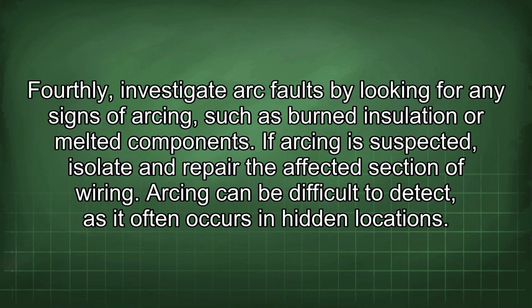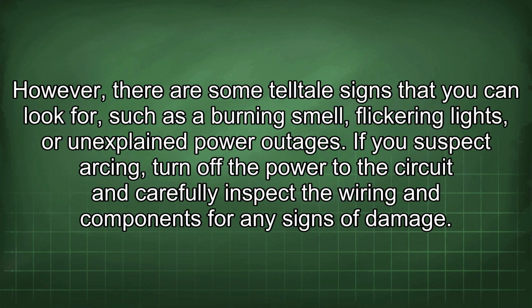Fourthly, investigate arc faults by looking for any signs of arcing, such as burned insulation or melted components. If arcing is suspected, isolate and repair the affected section of wiring. Arcing can be difficult to detect, as it often occurs in hidden locations. However, there are some telltale signs that you can look for, such as a burning smell, flickering lights, or unexplained power outages. If you suspect arcing, turn off the power to the circuit and carefully inspect the wiring and components for any signs of damage.